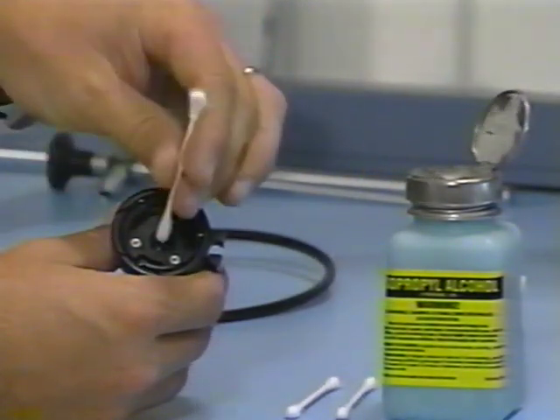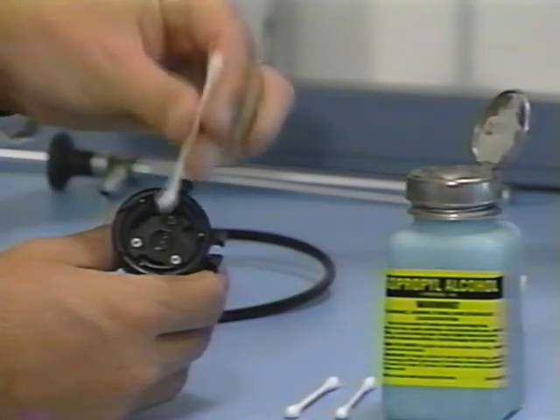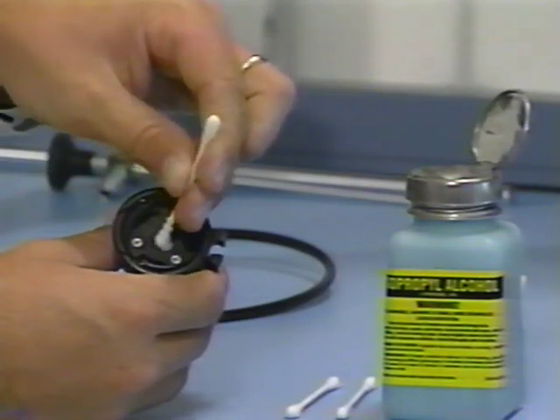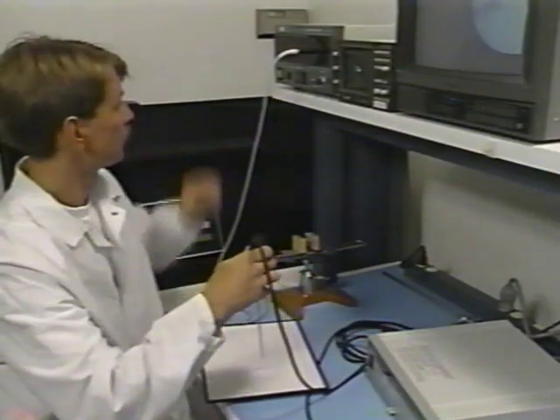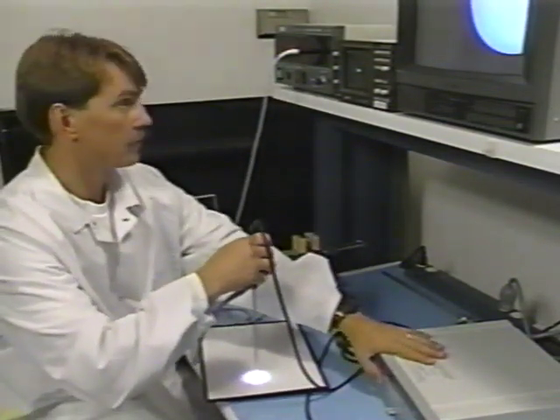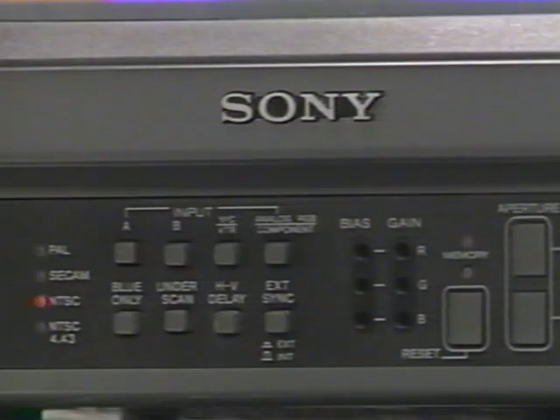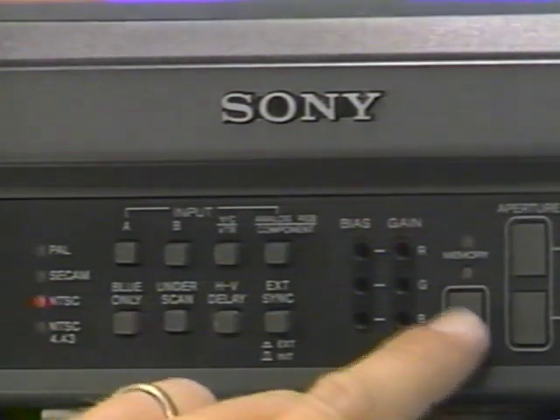Complaints of spots or a blurred picture should lead you to the cotton swab and alcohol for the lenses. The optics of the camera head and the endoscope both need to be considered. A dark image can also be the result of dirty optics and/or broken fibers in the scope or light guide cable. Poor color or inaccurate color reproduction may simply be that the camera was not properly white balanced or that the monitor is not properly adjusted. Re-white balance with every piece of equipment in place. If the problem is the monitor, press the reset button on the monitor and refer to the operator's manual for making further adjustments.